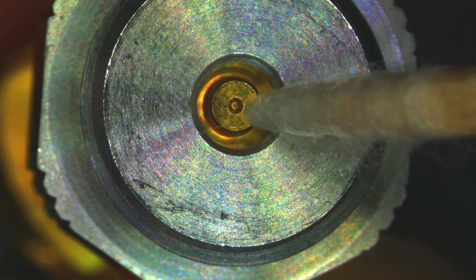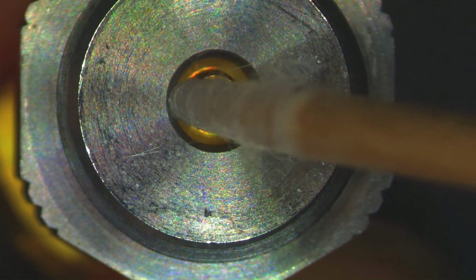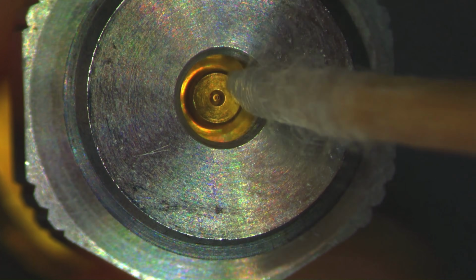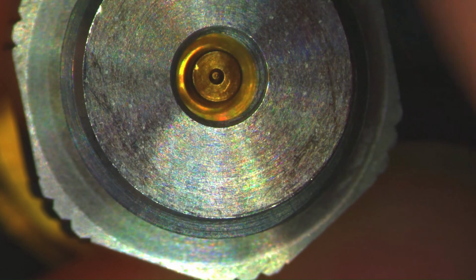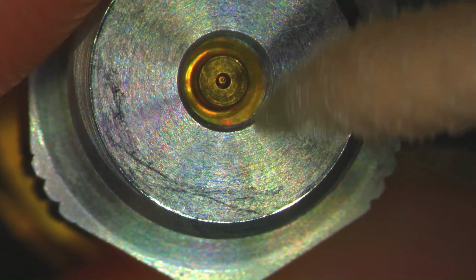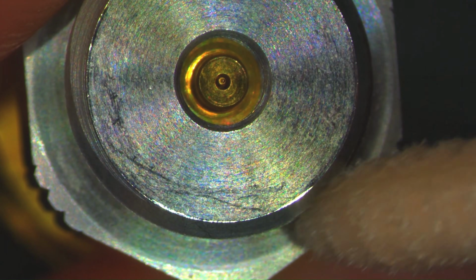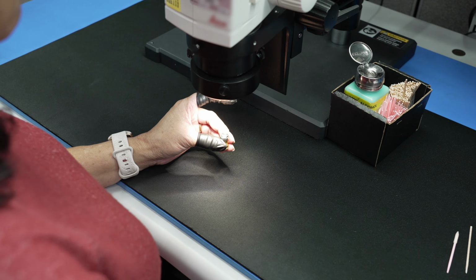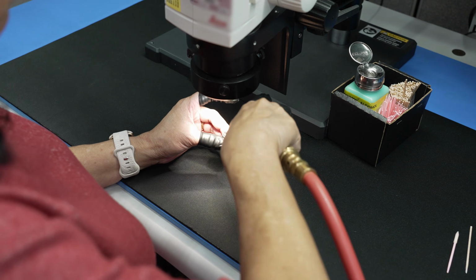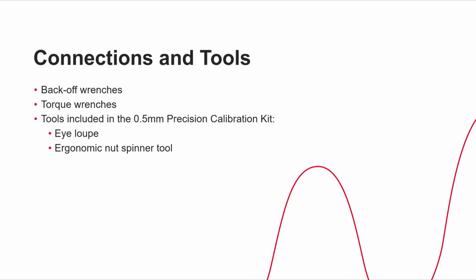A male ruggedized coaxial device, which is shown here, can be cleaned following the same steps. A male ruggedized device has a large nut with both internal and external threads. After cleaning, apply compressed air to the device. To connect the device, use back-off wrenches and calibrated torque wrenches. Additionally, the 0.5 mm precision calibration kit contains two specific tools we will demonstrate. These are the eye loupe for part inspection and the ergonomic nut spinner tool to help spin the male nuts.